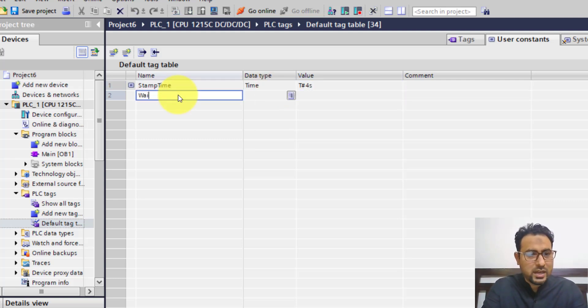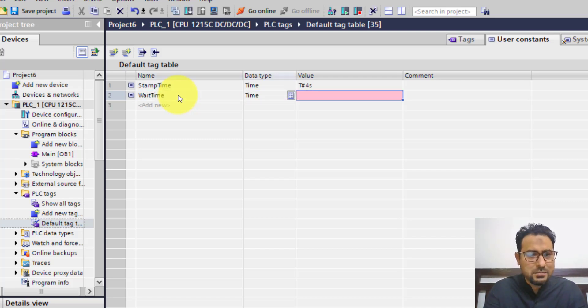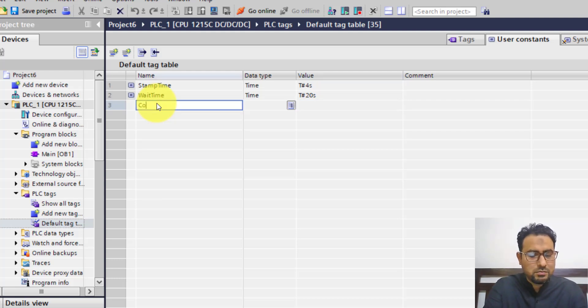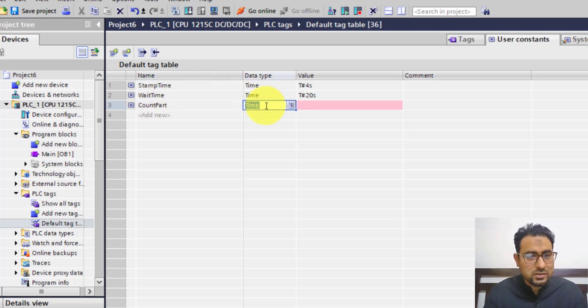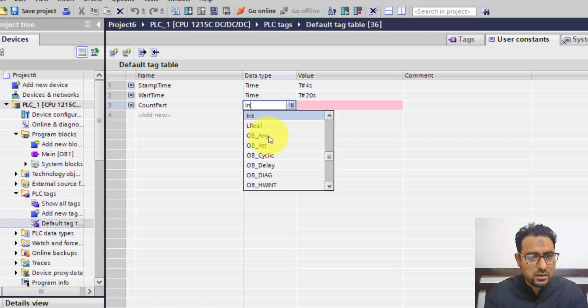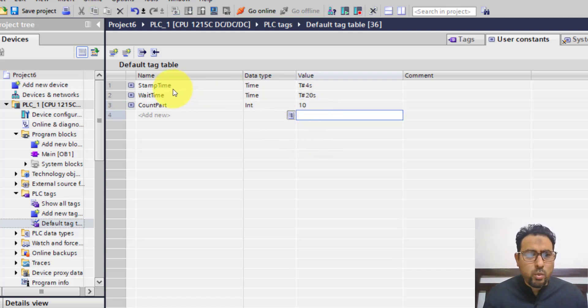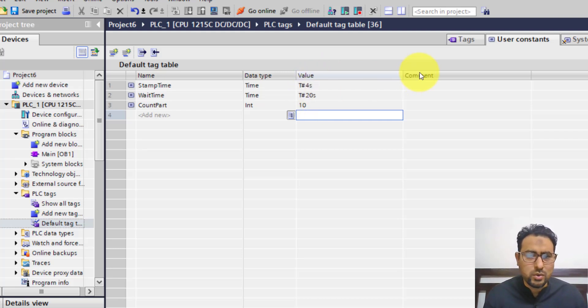Similarly, I'm going to define the wait time — data type time, value T#20S. And for the counter, I'll use the tag name count part, data type integer, value 10. Now, no matter where I'm using these preset values in my program, I can always come here and change the values, and it will automatically update in the program. So these are all my tags — now I can go to the main program and start programming.